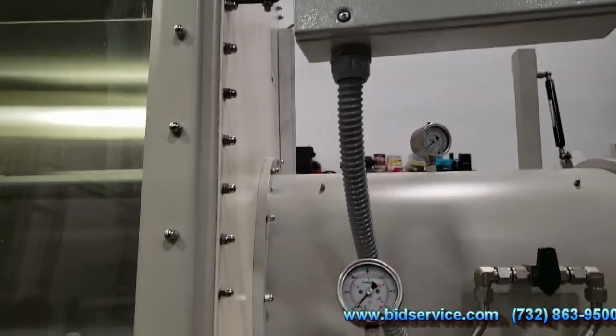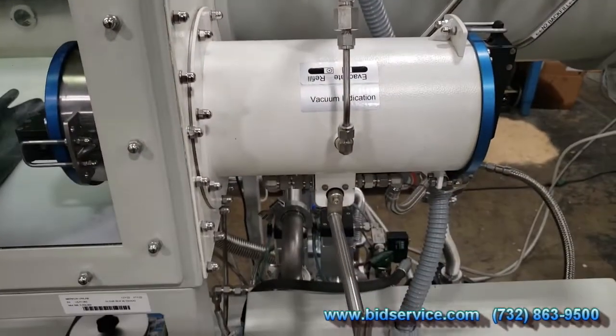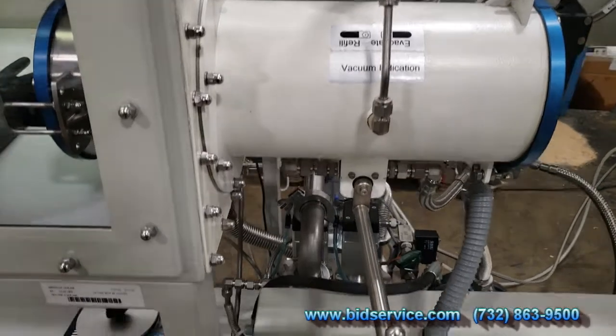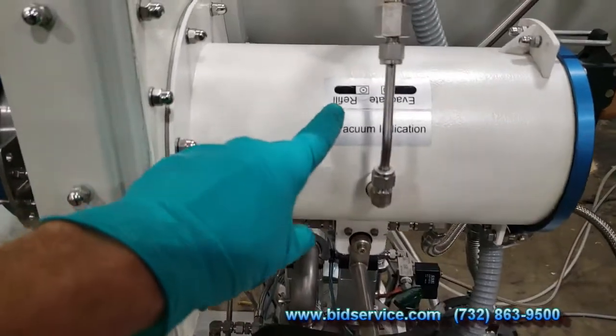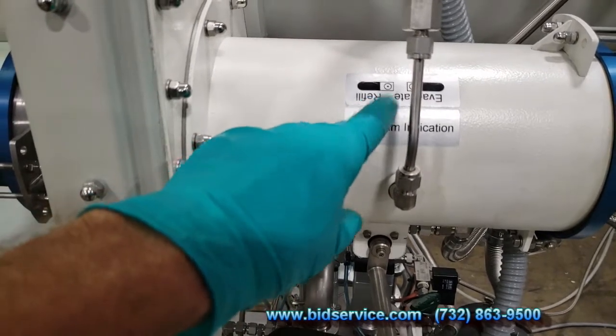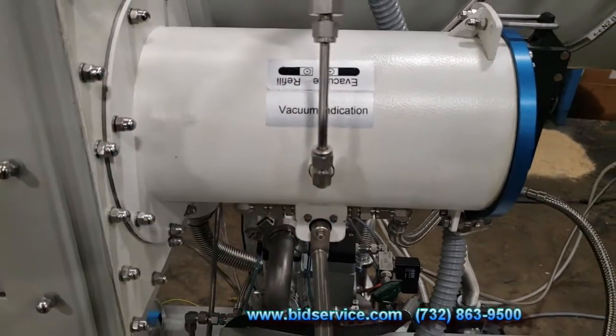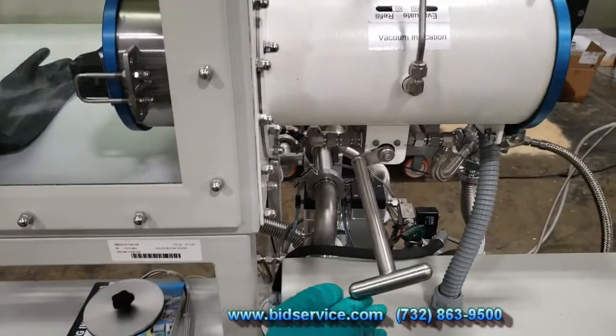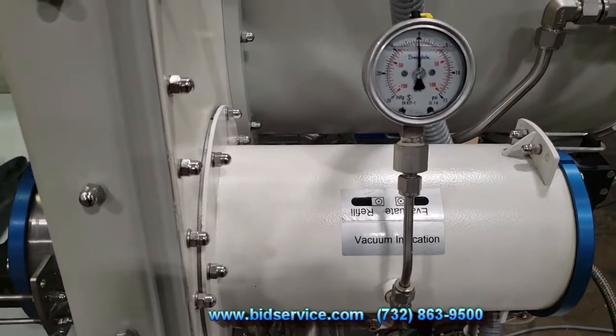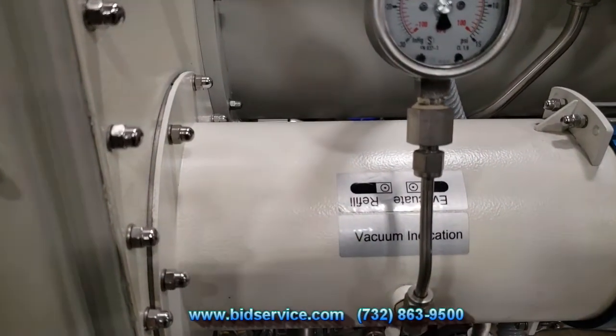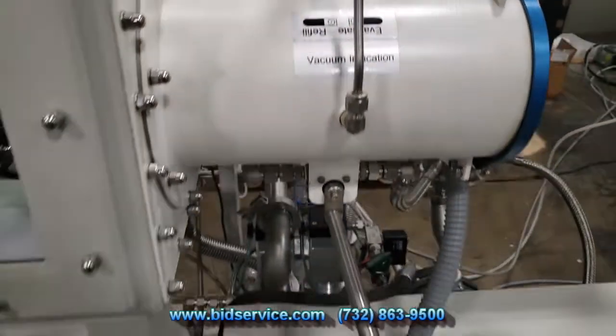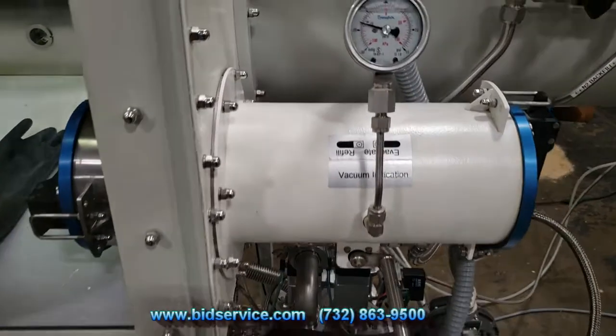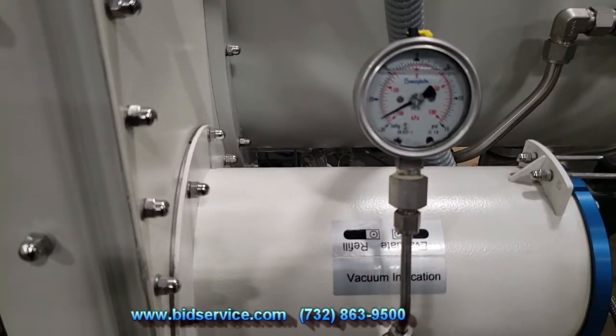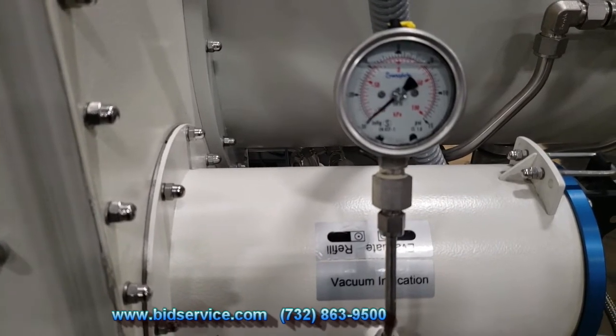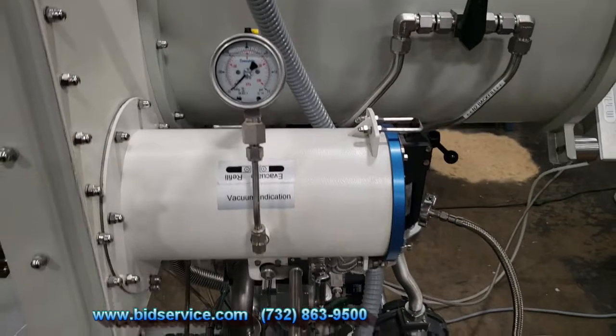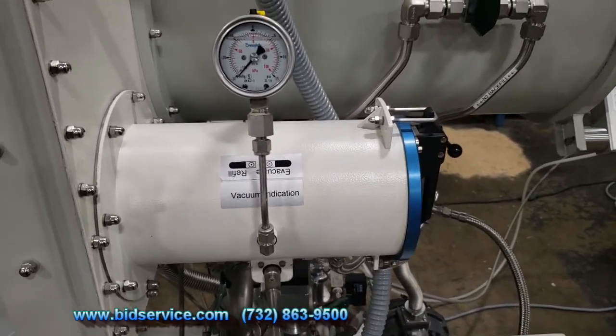I just want to point out one thing here too: the small antechamber has this handle added to it. Because of that, this is correct, although the writing is upside down. If you want to refill a box, for instance, you turn the handle in this direction, and you'll see that the pressure has come back up to atmosphere, 0 inches of mercury. Then we'll evacuate it by turning the handle in this direction. And you see it'll pump it out. I typically leave the system under vacuum, both the small antechamber and the large, in idle mode when we're not using it.